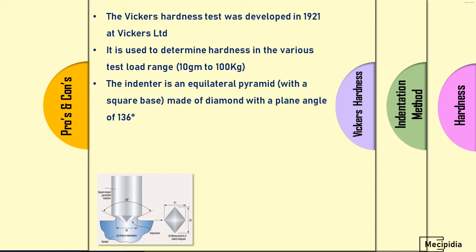One great advantage of this method is that the indenter is an equilateral pyramid diamond, cone-shaped at the bottom with a 136-degree angle. As you can see in the image below, the indentation will be in a square shape. Measuring the square shape diagonals D1 and D2 is very easy compared to Brinell and other hardness methods where a ball is used and measuring the circular indentation diameter can create some confusion. Here the measurement is very accurate and will not lead to any error.